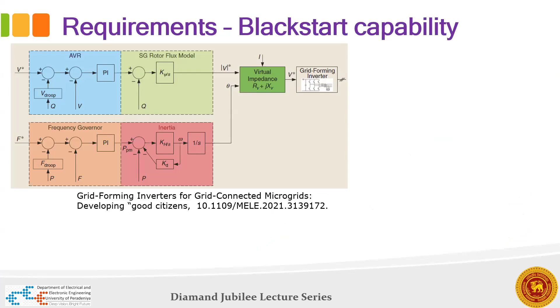If we're looking at a mini grid that can operate in off-grid and on-grid mode, you'll need black start capability. For that, there are now grid-forming inverters. The only difference is that the grid-forming inverter will have a virtual impedance if you want to connect them in parallel with other devices or generators.